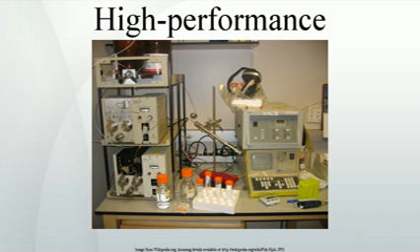Narrow-bore columns, 1 to 2 mm, are used for applications when more sensitivity is desired, either with special UV-vis detectors, fluorescence detection, or with other detection methods like liquid chromatography mass spectrometry. Capillary columns, under 0.3 mm, are used almost exclusively with alternative detection means such as mass spectrometry. They are usually made from fused silica capillaries, rather than the stainless steel tubing that larger columns employ.